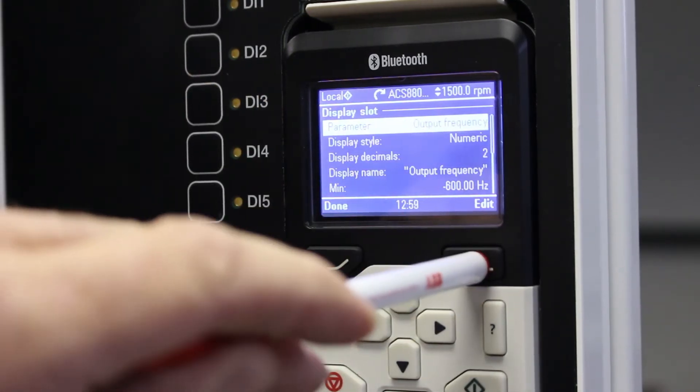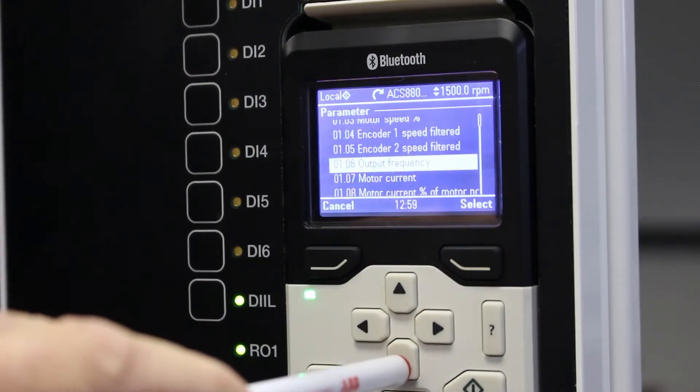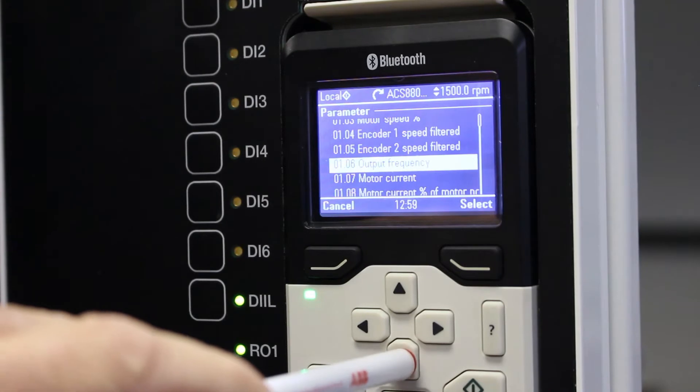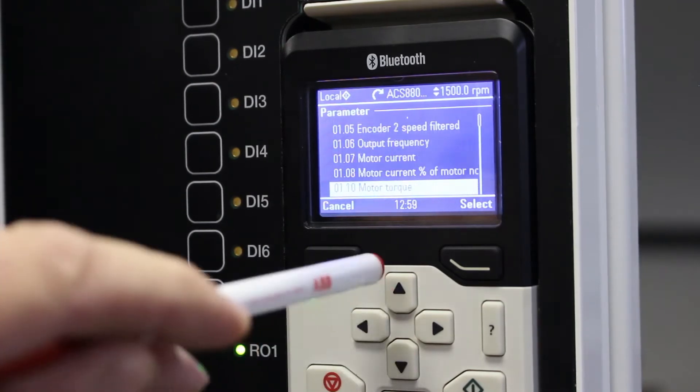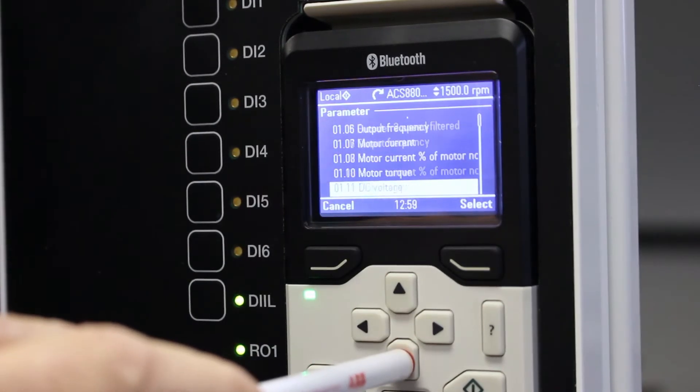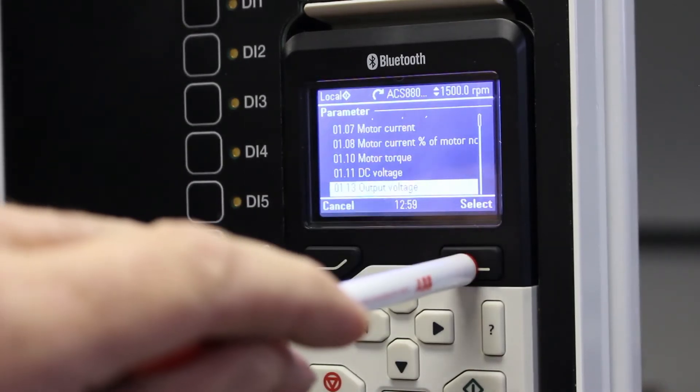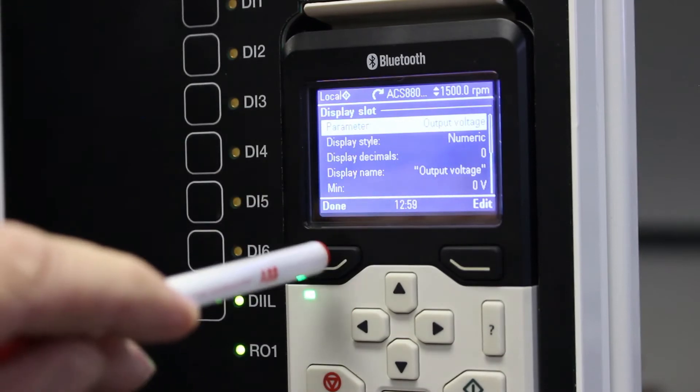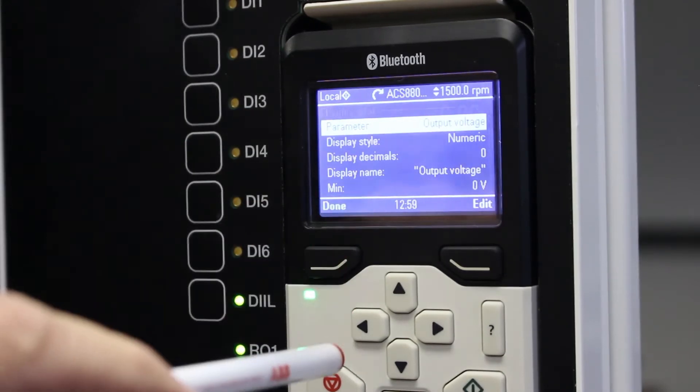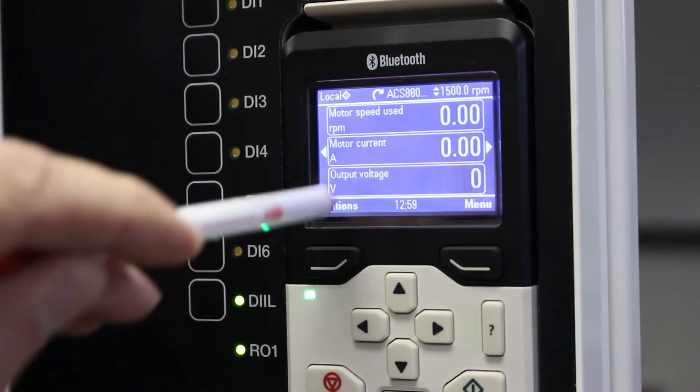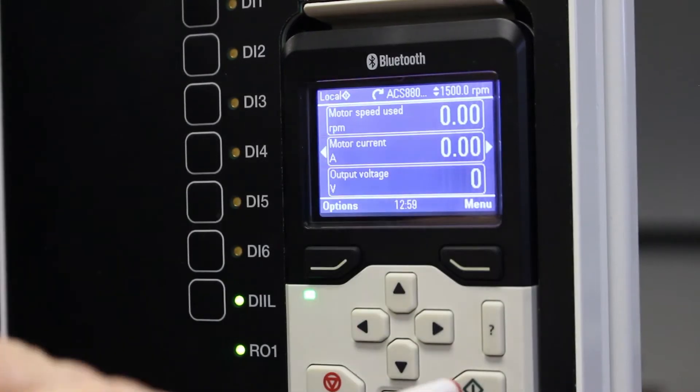I don't want output frequency anymore, I want to change it to motor voltage which will be output voltage. So I look for it over here in group one. Output voltage, I select it, I see okay it's output voltage and I say done and done and now I've got output voltage.